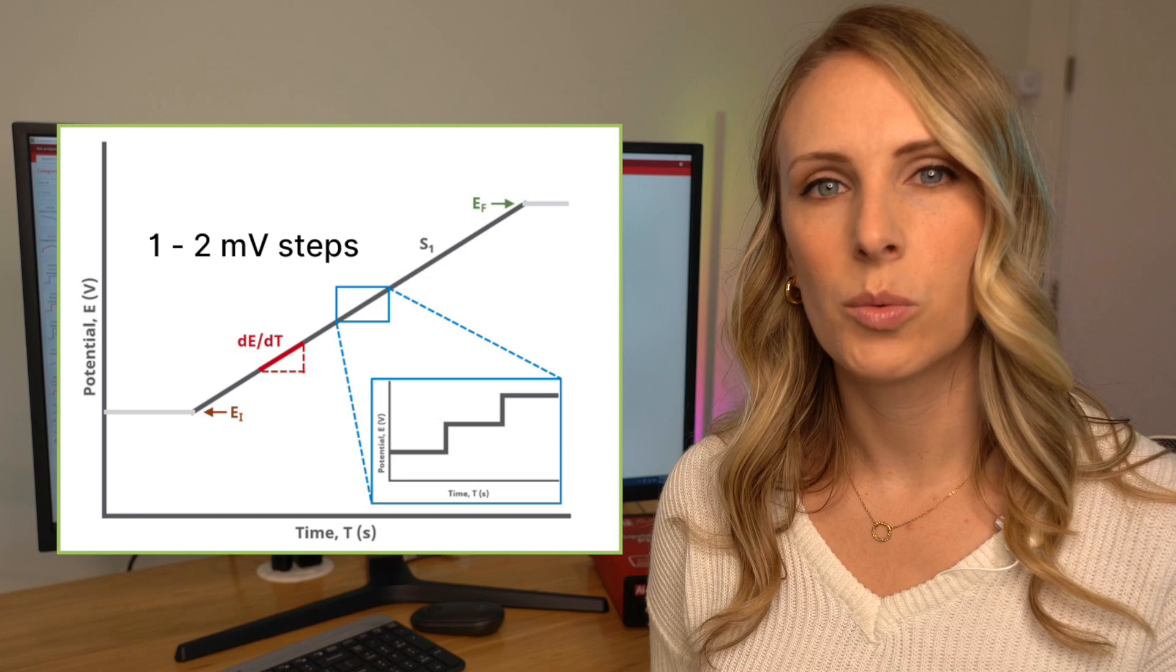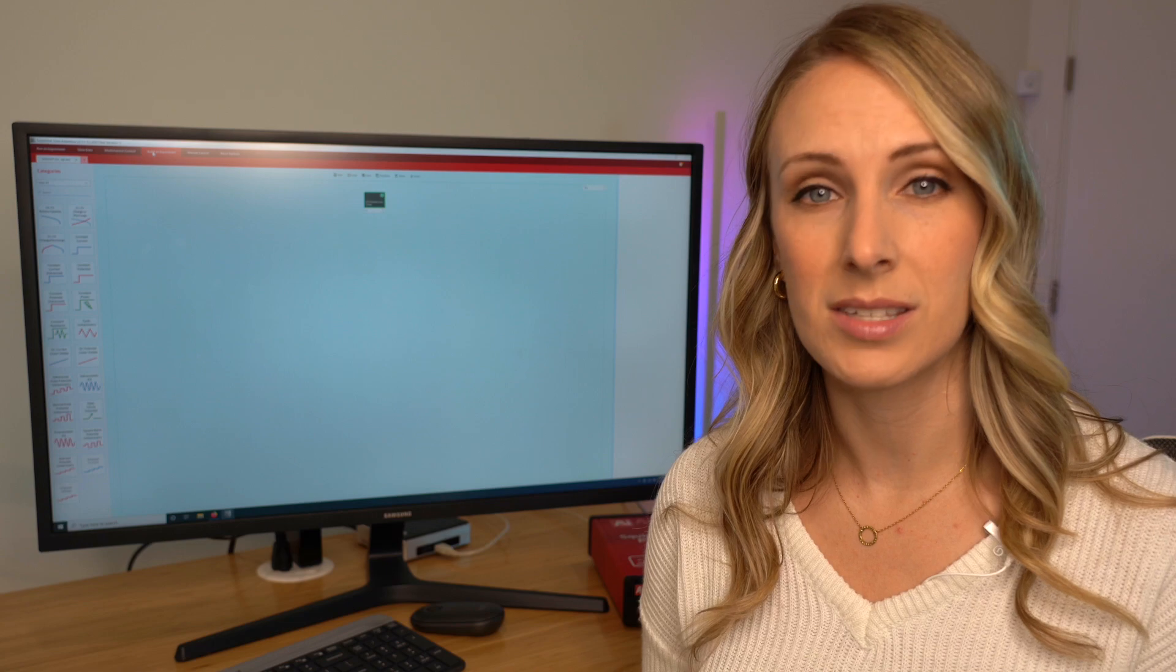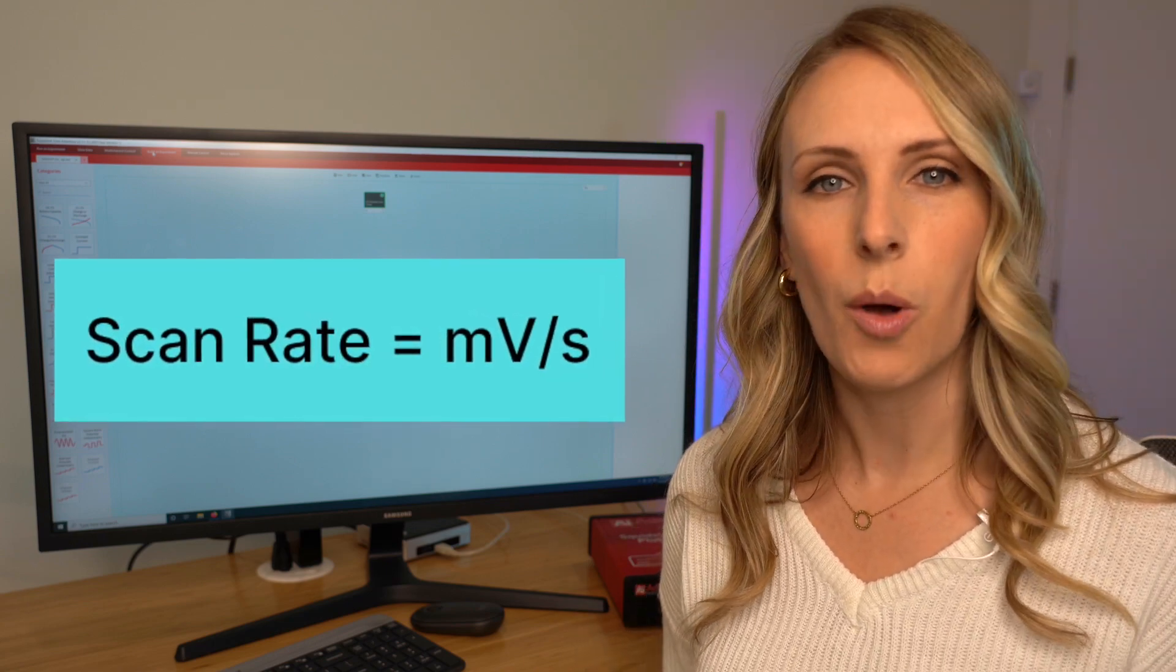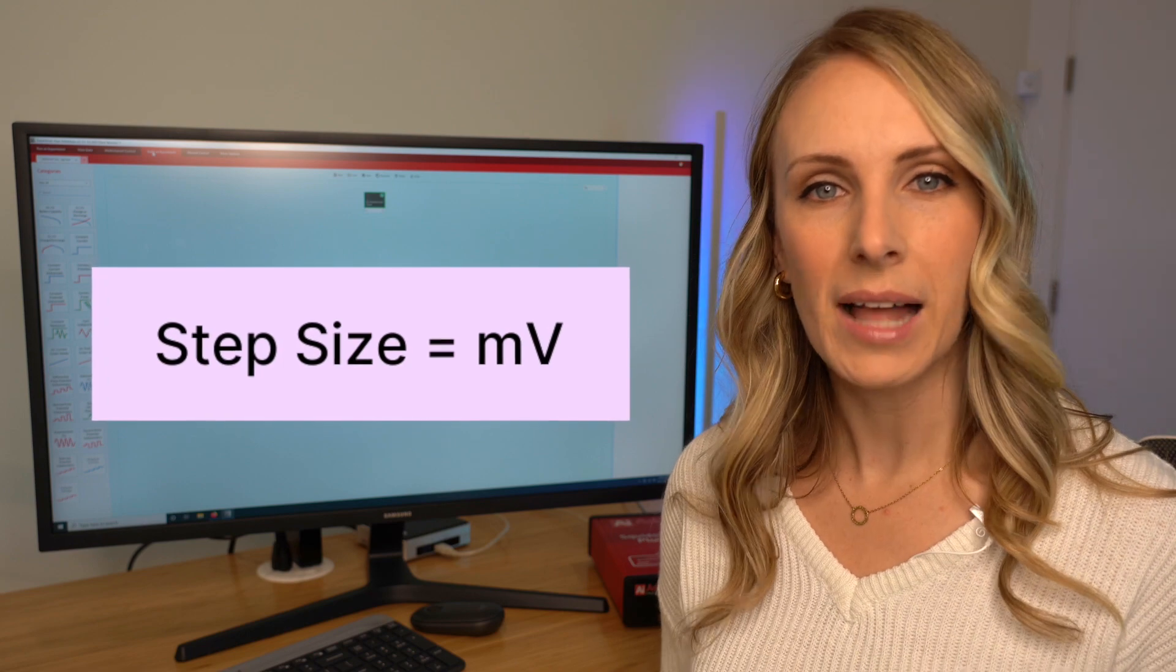In this potentiostat, however, you can change that step size. So when you're setting your settings for a CV or LSV, you want to pay particular attention to not just the scan rate, which is the scanning rate of the voltage in millivolts per second, but you also want to pay attention to that incremental voltage step size measured in millivolts. Balancing these is essential for resolving the data that you need. Let me explain why that is.